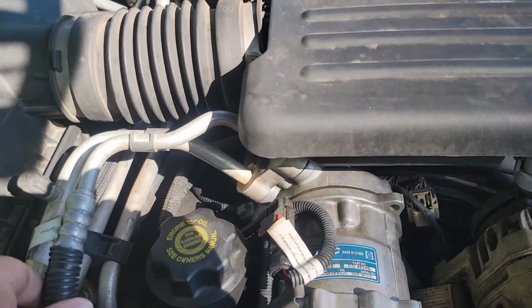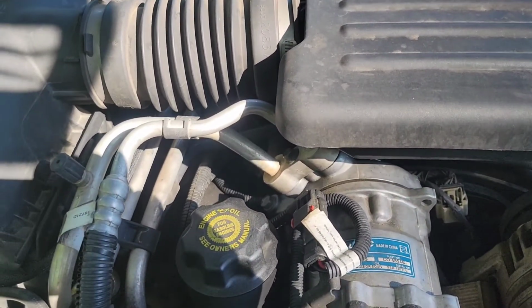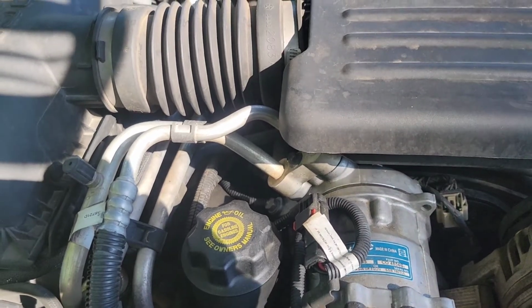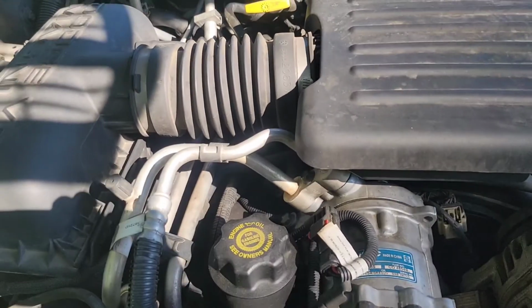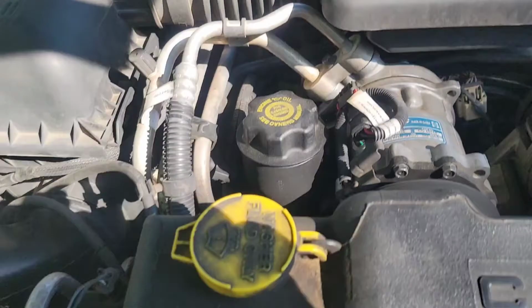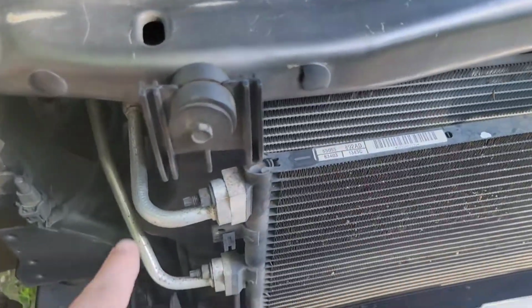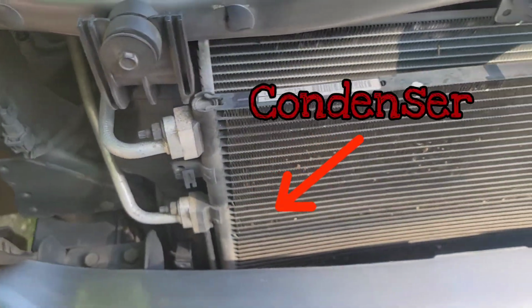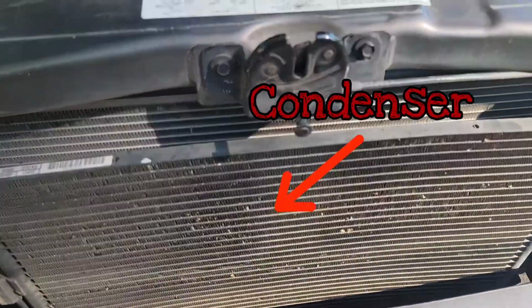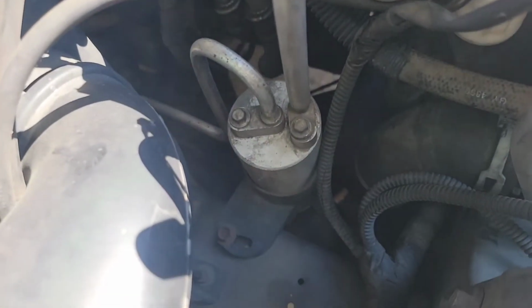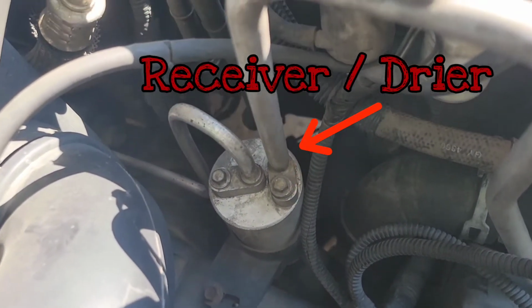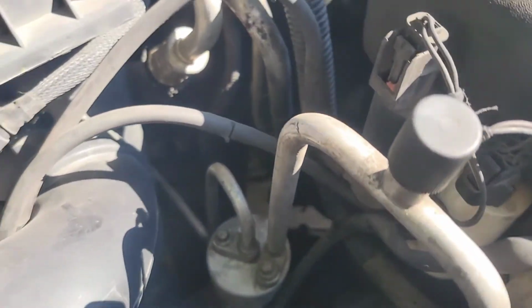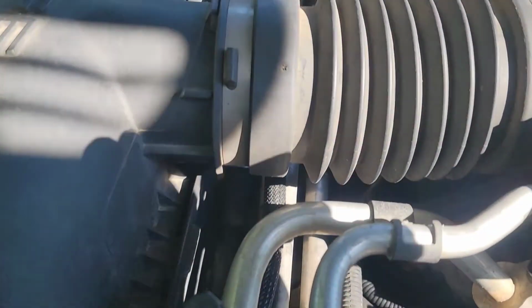The refrigerant leaves the compressor as a high pressure, high temperature vapor on its way to the condenser. By removing the heat via the condenser, the vapor becomes a high pressure, lower temperature liquid. Moisture and contaminants are removed by the receiver dryer, and the refrigerant is stored until needed.